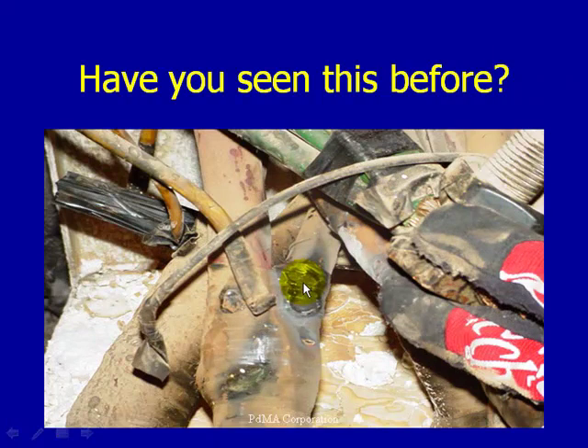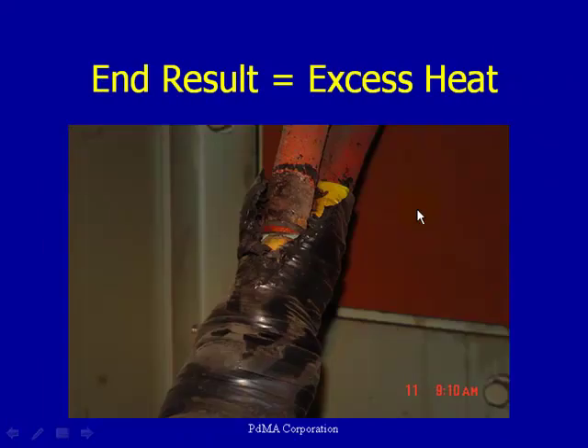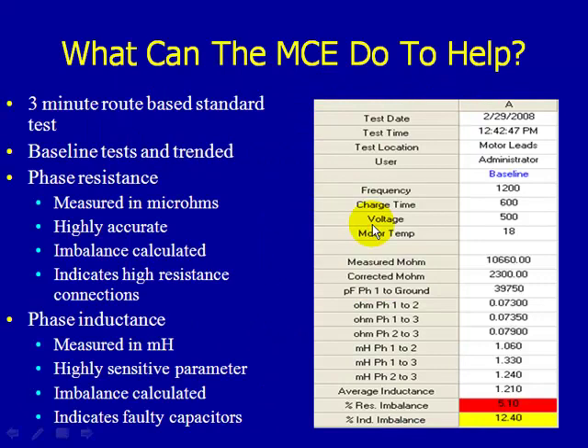Poor connections create excess heat. We can see evidence of excess heat in multiple images, and through a thermographic image we can clearly see the difference — one phase is running much higher in temperature than the other two phases, which is a clear indicator of a problem in the power circuit.